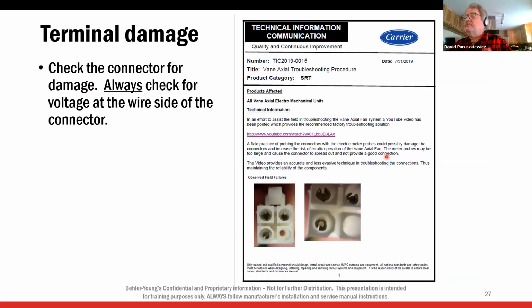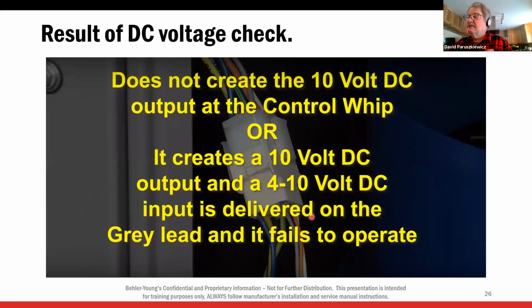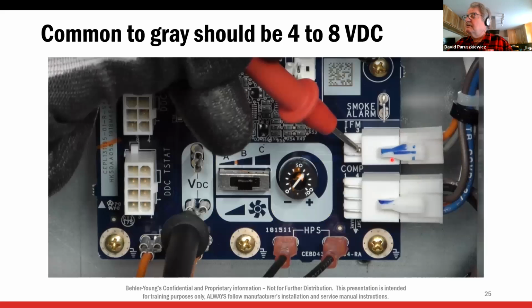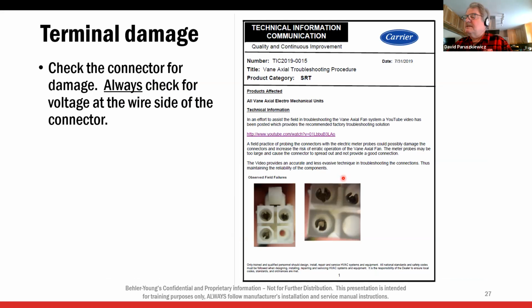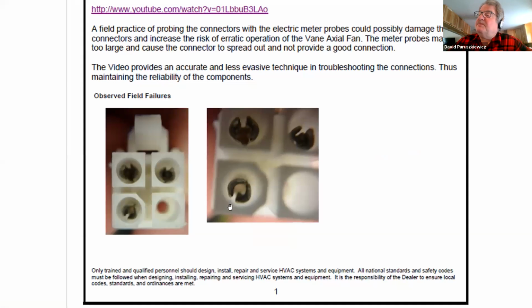Okay. This is a bulletin that had come out on these units. This little plug here is this plug right here. And what happened is somebody takes their big old honking leads from their meter and shoved them in the front of this plug, and look what happens. So they created a problem. Do not put your meter leads in the front of that plug. Put them in the back of the plug.